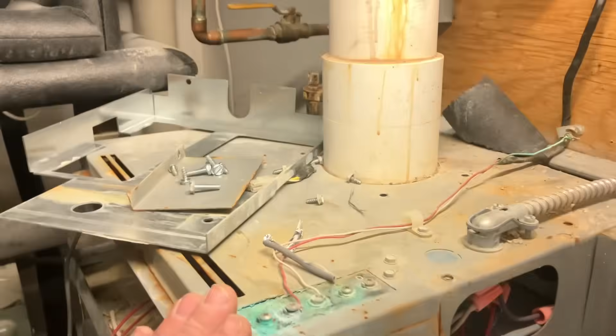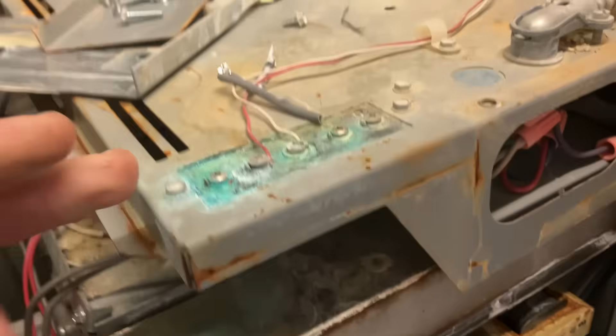All right, let's review. Spoke to tech support at NTI. I actually have a contact number, so he's like the sales rep for the area. But based on the overall condition of the water damage from above and evident from the terminal block, terminal strip on the outside top right front, no bueno. Transformer, terminating block, fan wall ignition control, the Sentry controller, the pressure switch, manifold limit, high temperature limit, automatic air valve, which probably was like that from the beginning, but whatever. And the damage, residue on everything here. And the fact that she was initially installed in 2008, no bueno.